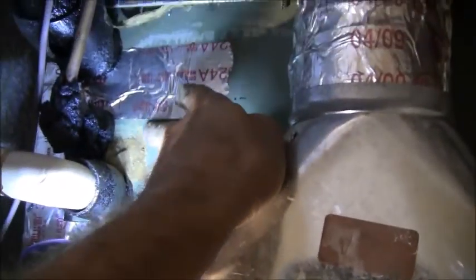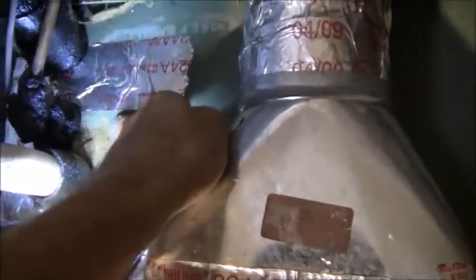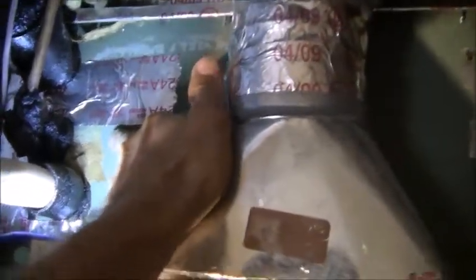Now, before I drilled that hole, first of all, I looked at the unit. If you look at the way the unit is constructed, you can see the liquid line is here. Let me get a flashlight. You can see this a little bit better. Okay. Now, this is the liquid line. My finger is touching the liquid line. This is liquid refrigerant coming in. It's supposed to be going to an expansion valve, some type of metering device inside of this unit. Actually, I don't think it's an expansion valve. I think it's a fixed metering device. That's my assumption. This here, where the insulated line is, that's the suction line where the vapor refrigerant is traveling back up. So here the refrigerant's coming down, here it's going up.